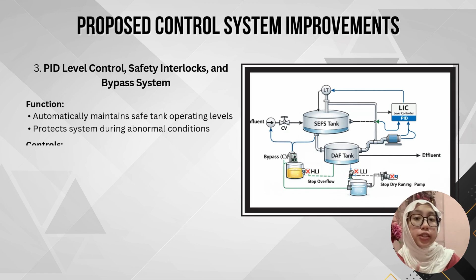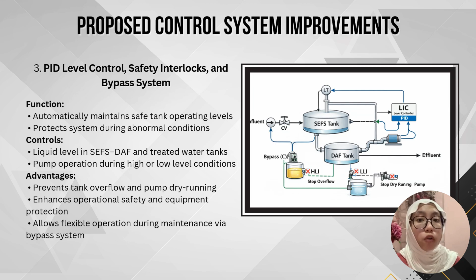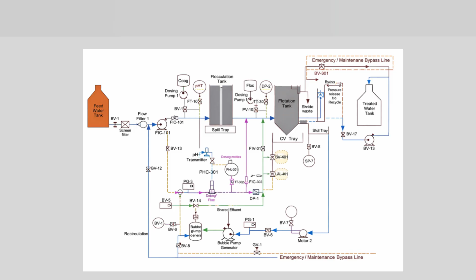Okay, lastly, for the third improvement, PID based level control is implemented together with the safety interlock and a bypass system. The level control maintains safe liquid levels in the SEFS DAF and treated water tanks. High and low level interlocks protect the pumps from overflow and dry running. In addition, the bypass system allows continuous and flexible operation during maintenance or abnormal conditions. It will improve the overall system safety and reliability.